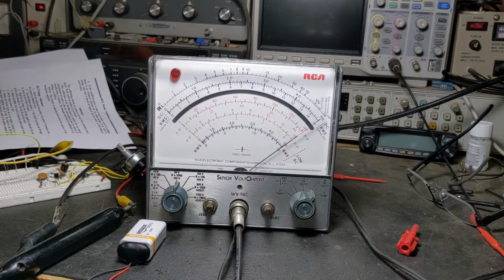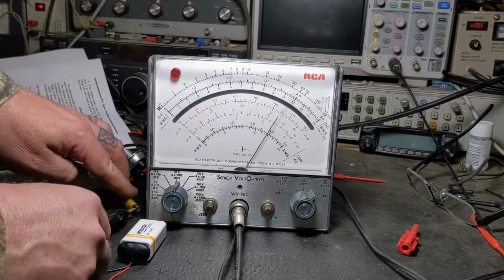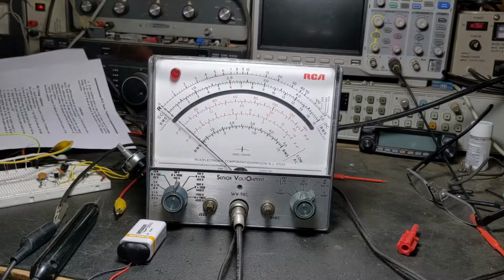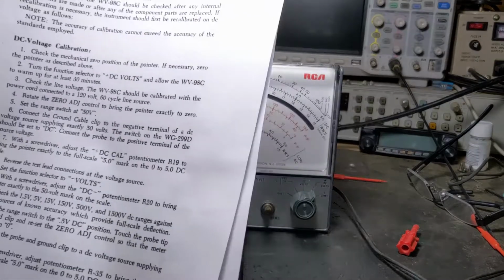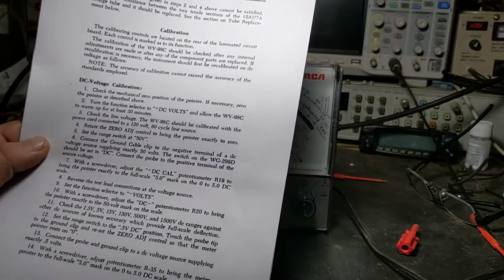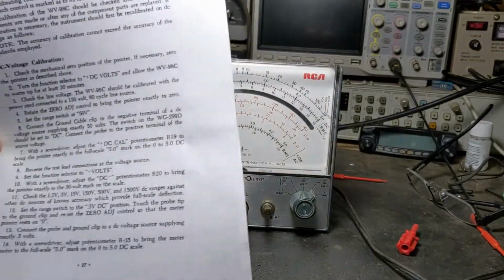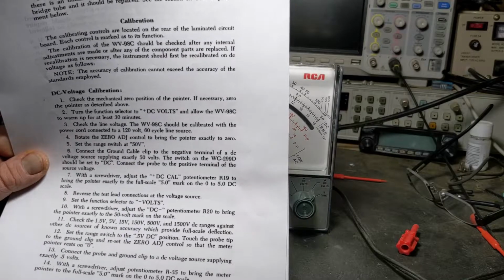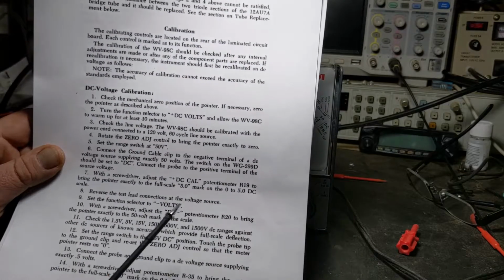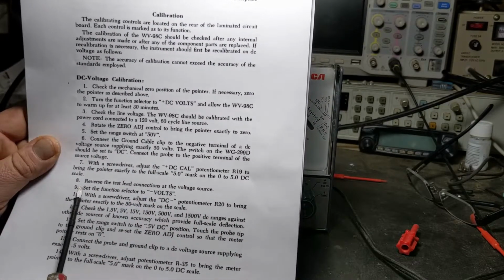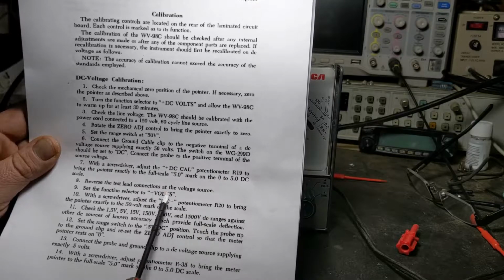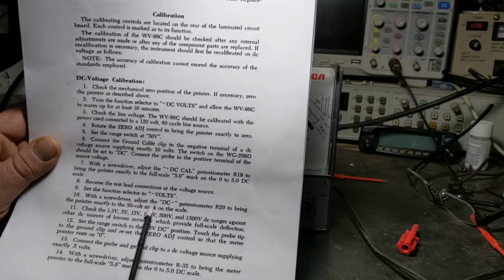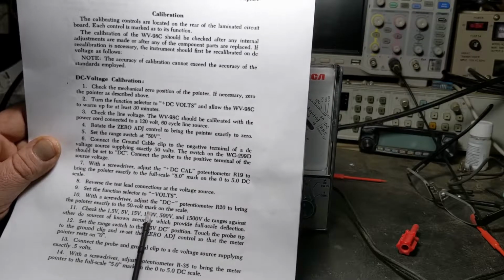I've not touched it, I promise. There's no adjustment needed. That's dead on 5.0. It's not bad. Well, that ain't bad. Okay, and then it says, well, if I had known that, I'd have gone in and off camera twisted it just a little bit. But the potentiometer on the back, you have to adjust to make that 5.0. Reverse the test leads and set it to negative volts. With the screwdriver, adjust the DC negative potentiometer R20 to bring the pointer to exactly 50 volts on the scale.